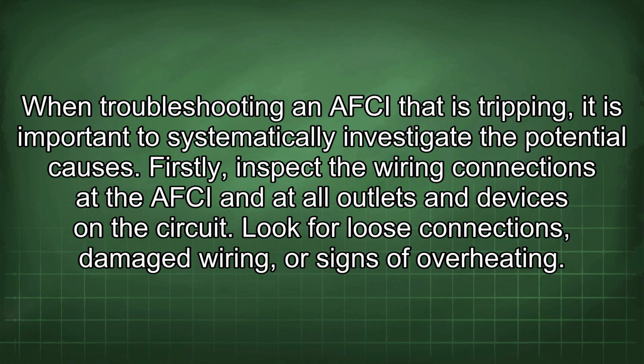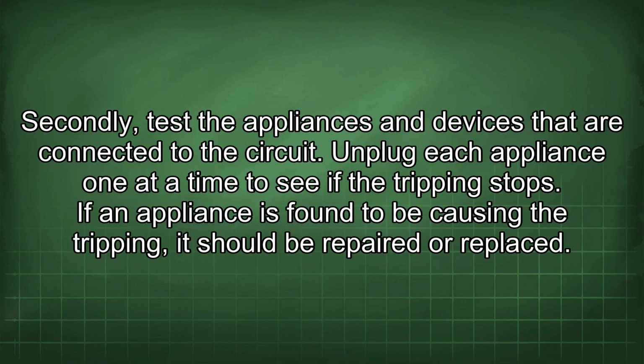When troubleshooting an AFCI that is tripping, it is important to systematically investigate the potential causes. Firstly, inspect the wiring connections at the AFCI and at all outlets and devices in the circuit. Look for loose connections, damaged wiring, or signs of overheating. Secondly, test the appliances and devices that are connected to the circuit. Unplug each appliance one at a time to see if the tripping stops. If an appliance is found to be causing the tripping, it should be repaired or replaced.